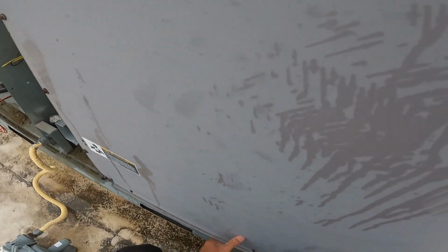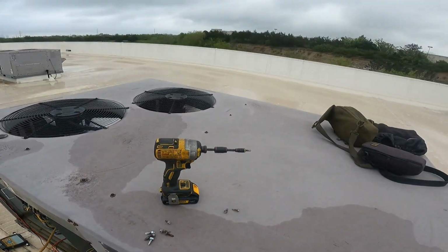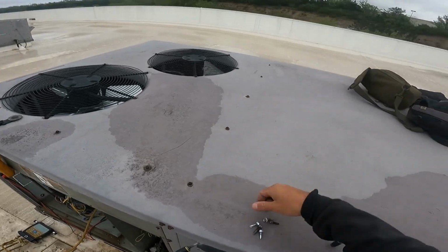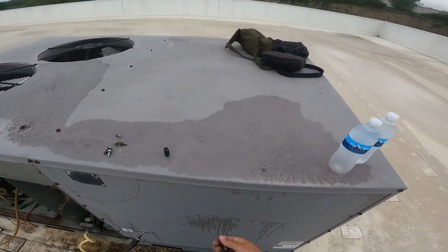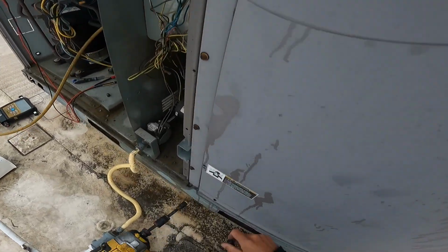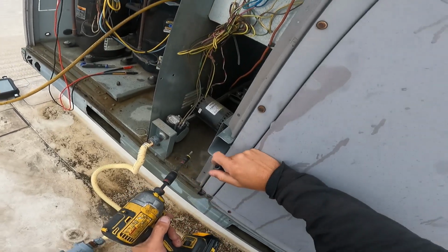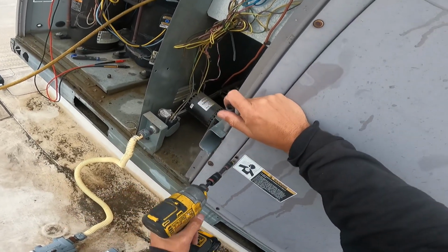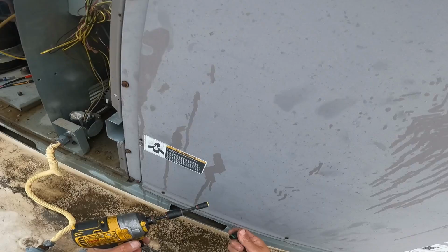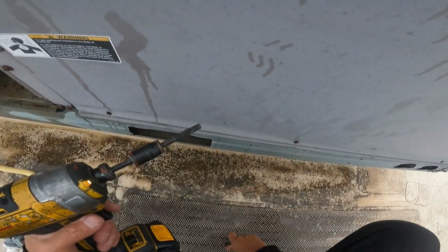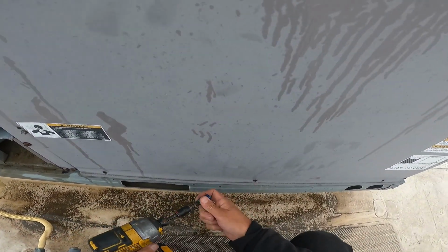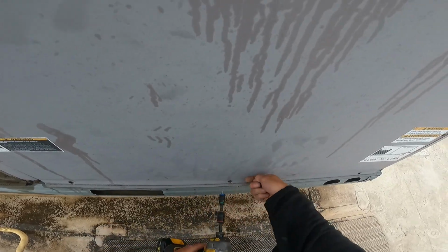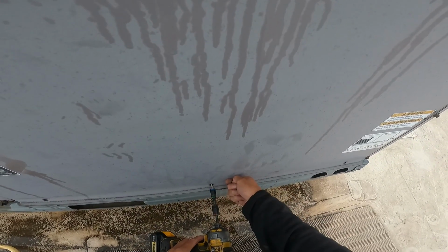So this is gonna be a test fire, okay? Test fire! Which means we're gonna fire it off, and I'm gonna go ahead and turn the gas off to it, because it cannot run. You don't want it to run with a hole in the heat exchanger, because people are gonna wake up dead.